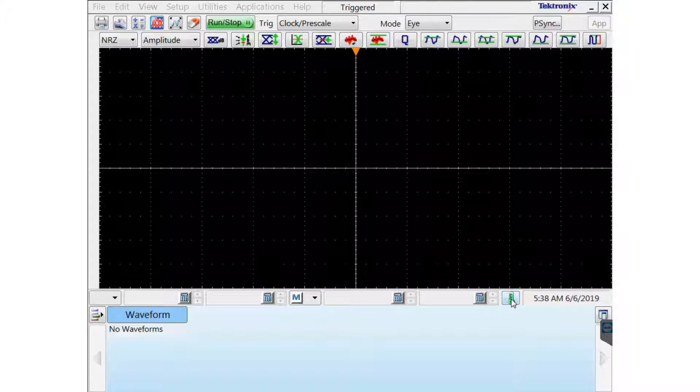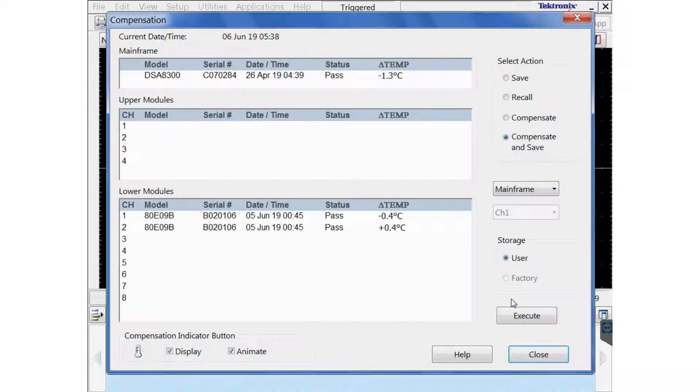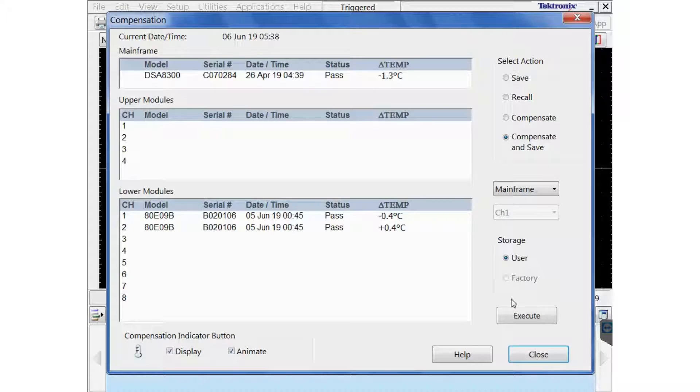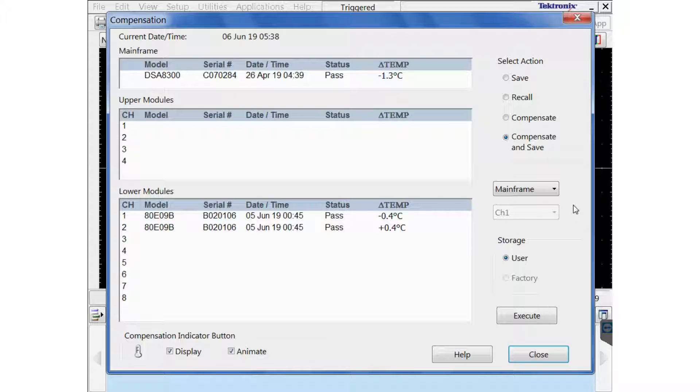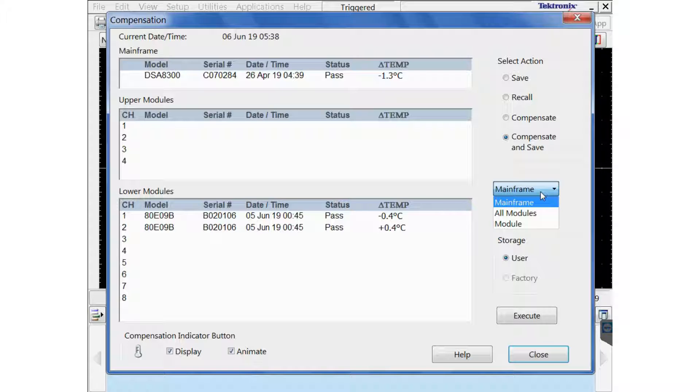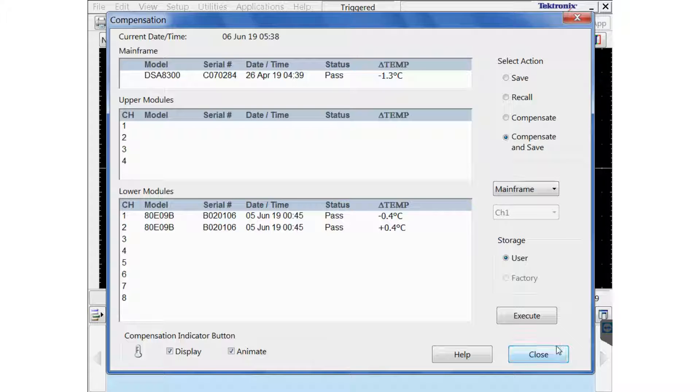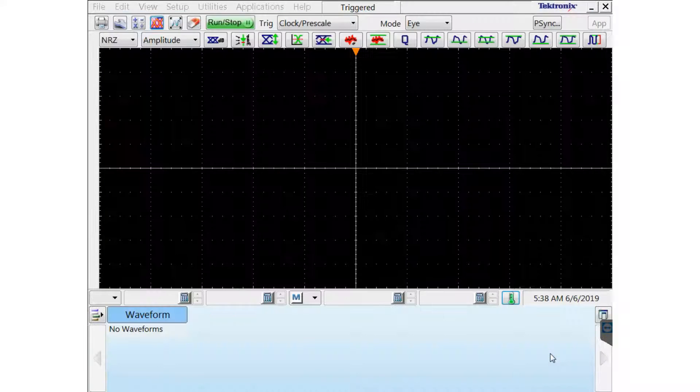Before you do any de-skew, you should check the compensation. Click on the thermometer and make sure your mainframe and your modules are compensated correctly. If they're not, you just click the Execute button.